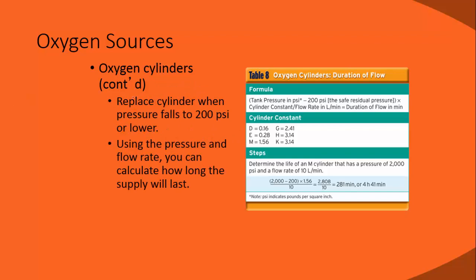There's a means of calculating how long a tank will last, and so we want to give you some references here. This is really important when you have long transport times and limited amounts of oxygen. Flight medicine is a good example of that. It's also important if you're using high flow O2, a high oxygen mix. It's CPAP for long transport - CPAP is going to keep the airways open, and it uses a lot of oxygen when it's flowing through. It's basically like it's wide open. So we do want to be aware of that.